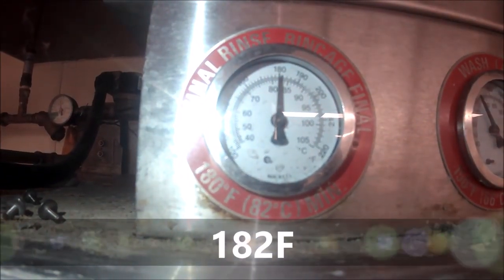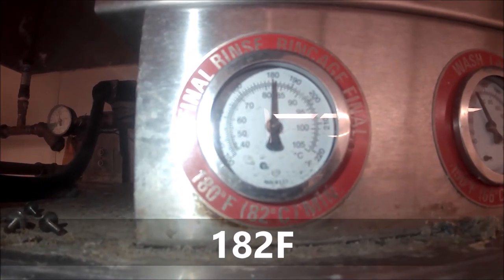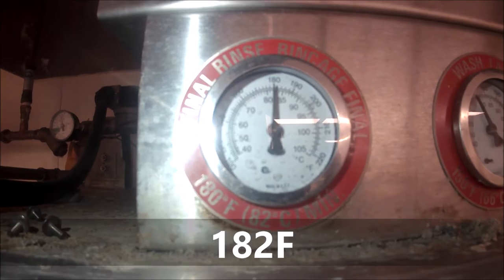Now our rinse is at about 182 Fahrenheit. I'm going to run like 10 more cycles. I ran about 5, just to make sure we don't overshoot the temperature. I'll monitor this unit very closely.